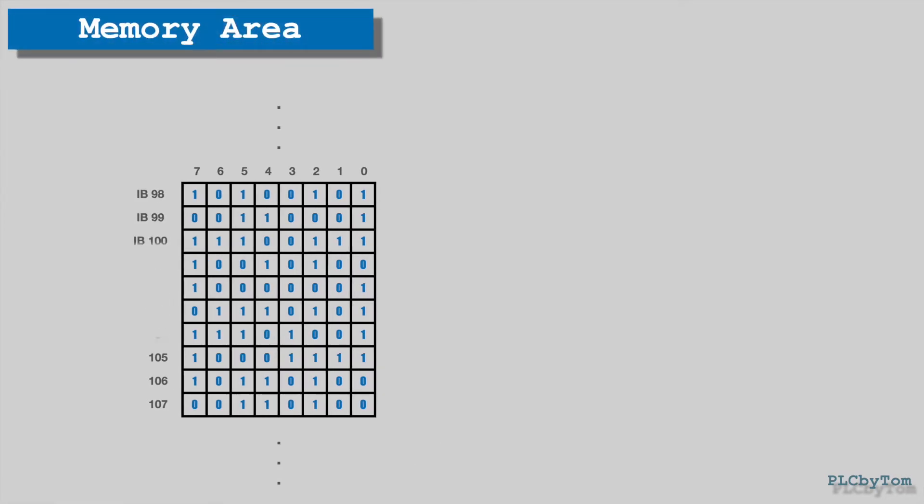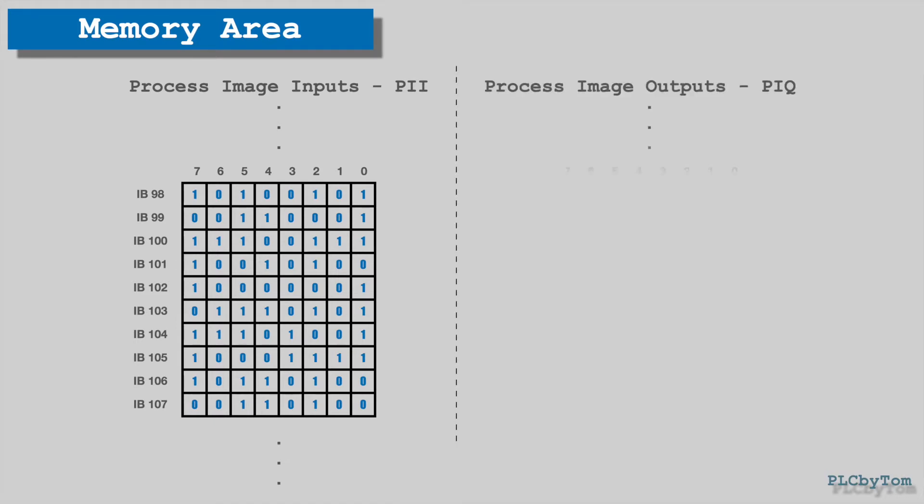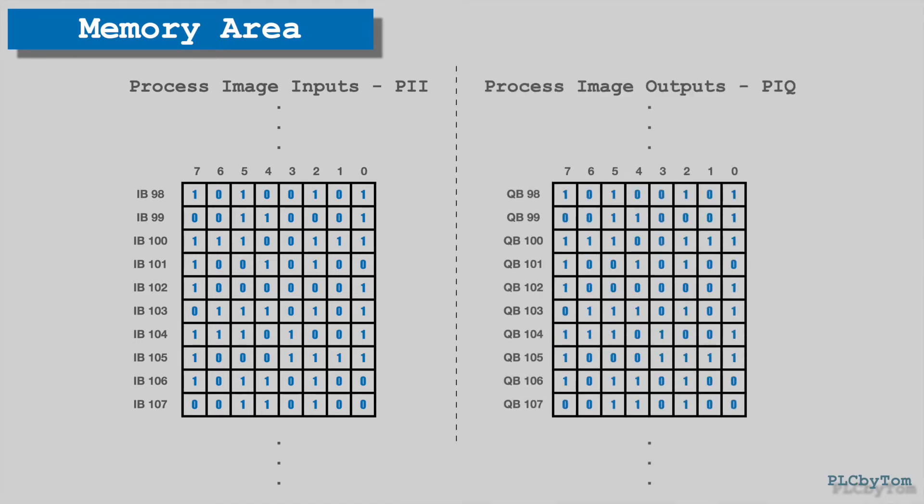There are different memory areas. There is a memory area reserved for inputs, and it is called process image inputs or shorter PII. Also there is a memory area for outputs, called process image outputs or shorter PIQ. Here we noticed that bytes are numerized and, by letter I or Q, it assigns to what memory area is related.